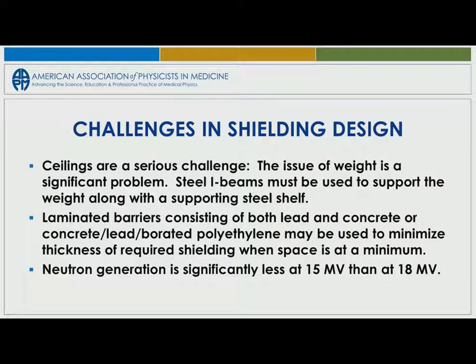But the ceilings are a serious problem, so you wind up with some type of lamination between lead and concrete. And if you're going to have to add lead to an existing room, are you going to put lead on the inside or the outside? You put your lead on the inside of the room because you don't want photoneutron production on the outside of your room. So you always add your lead to the inside of the room. If you want to be nice to your patients, then you cover that up with a layer of borated polyethylene.